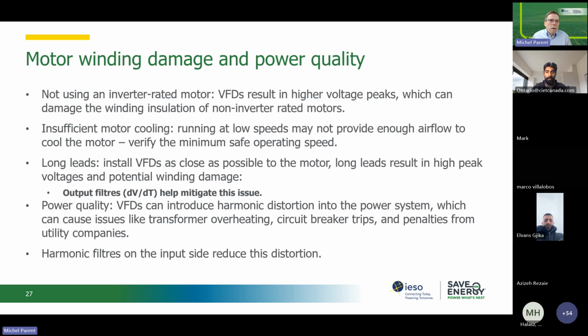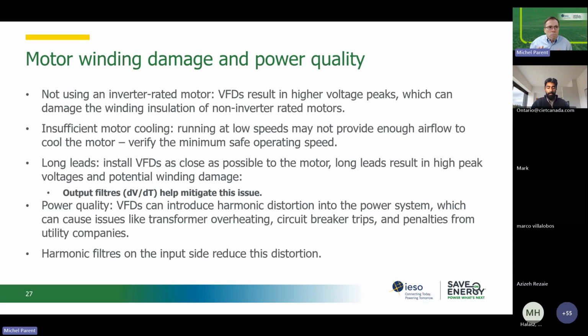So very quickly, the other problem is motor winding damage and power quality. A VFD will have much higher voltage peaks than a motor that's run without a VFD. So that's why you need an inverter rated motor, because non-inverter rated motors will overheat the winding. The winding insulation, the thermal insulation, is not as good, and it will short. So that's the reason why you need those inverter rated motors. You can use the infrared camera to check the surface temperature of your motor. It's class F. If it's above 105, you know that you're on a trend to burn out the winding. So again, if you've got the proper tool, it can be diagnosed.